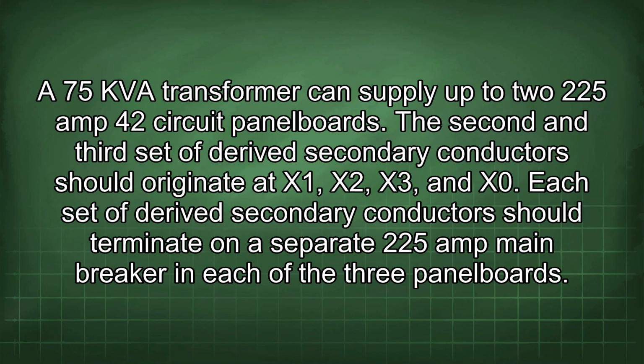A 75 kVA transformer can supply up to two 225 amp 42 circuit panel boards. The second and third set of derived secondary conductors should originate at X1, X2, X3, and X0. Each set of derived secondary conductors should terminate on a separate 225 amp main breaker in each of the 3 panel boards.